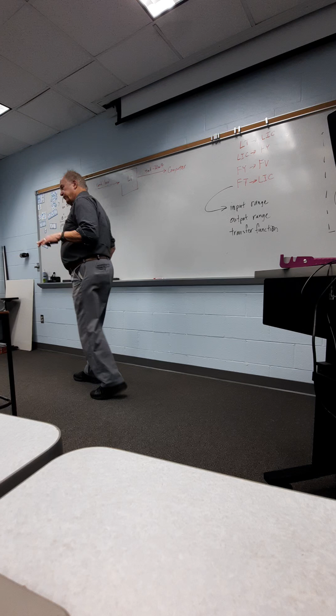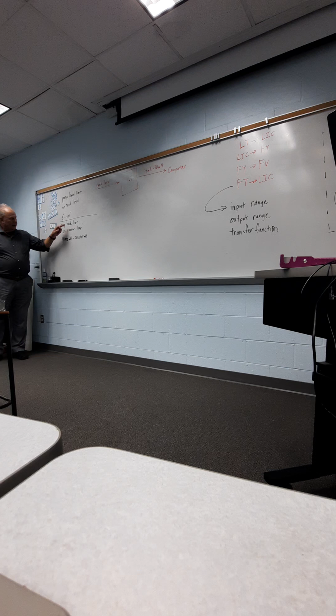So there's a proportional band limit that no matter how wide I make my proportional band, my equations fit that. I'm limited to this anyway. I'm never going to go outside the 0 to 10 inch range. So I have a proportional band limit that's fixed. It cannot be larger than that. Proportional band limit on the current loop is 4 to 20 milliamps, because anything outside there is an alarm.